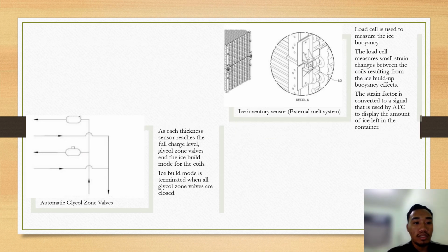The third accessory is the automatic glycol zone valves. As each thickness sensor reaches the full charge level, glycol zone valves end the ice build mode for the coils. Ice build mode is terminated when all glycol zone valves are closed.